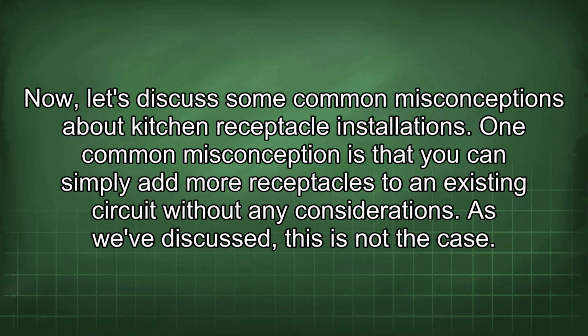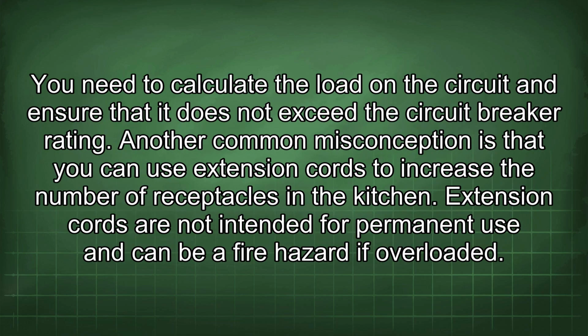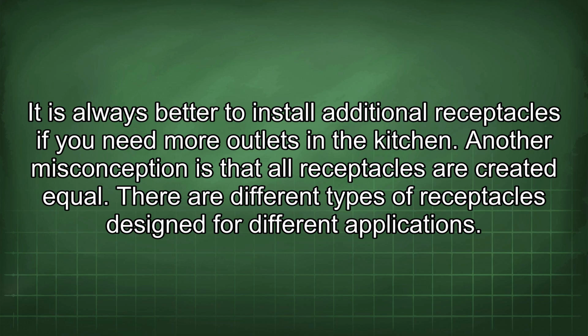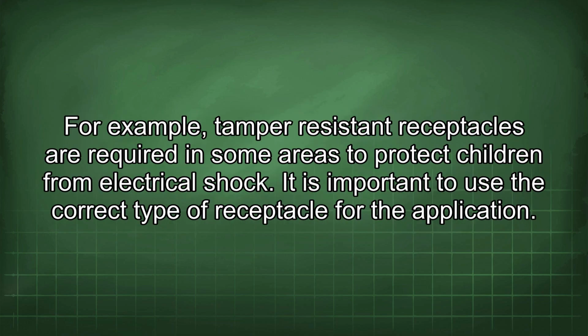One common misconception is that you can simply add more receptacles to an existing circuit without any considerations. As we've discussed, this is not the case. You need to calculate the load in the circuit and ensure that it does not exceed the circuit breaker rating. Another common misconception is that you can use extension cords to increase the number of receptacles in the kitchen. Extension cords are not intended for permanent use and can be a fire hazard if overloaded. It is always better to install additional receptacles if you need more outlets in the kitchen. Another misconception is that all receptacles are created equal. There are different types of receptacles designed for different applications. For example, tamper-resistant receptacles are required in some areas to protect children from electrical shock. It is important to use the correct type of receptacle for the application.